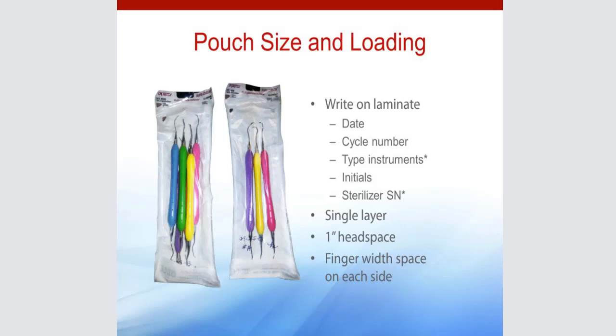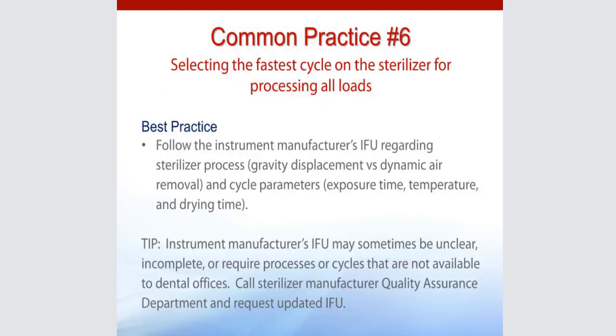Last but not least, your sterilizer serial number, especially if you have multiple sterilizers. If you have 2 Midmark units and all you write is Midmark, you don't know which one it was, and you have a failed BI and you have to go back and pull the instruments, if you don't have that serial number, you don't know which one it was.